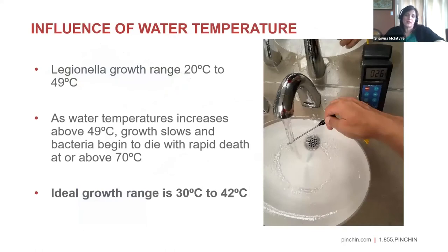Water temperature plays a huge role, especially within our buildings, in developing this bacteria. The Legionella growth range is between 20 to 49 degrees Celsius. As the water temperature increases above 49 degrees Celsius, the growth is going to slow down because it's outside its ideal growth range, and they're going to die off. Temperatures above 70 degrees Celsius will instantly kill them. They will not survive above that temperature. The ideal growth range is between 30 degrees to 42 degrees Celsius.